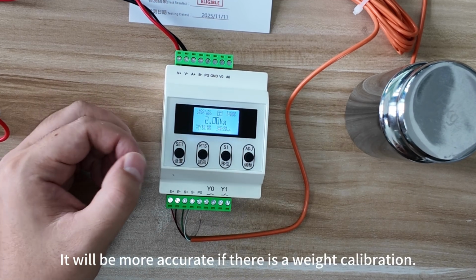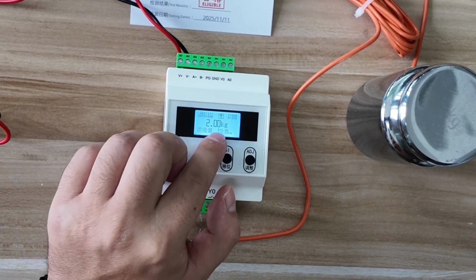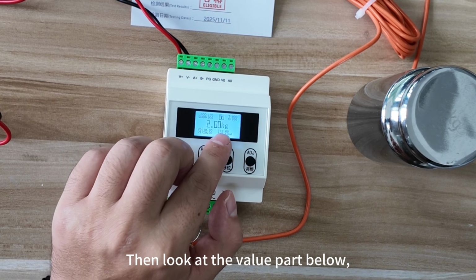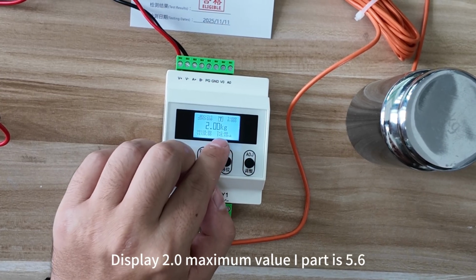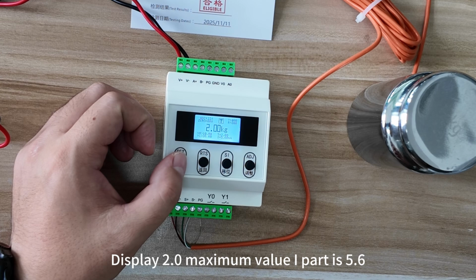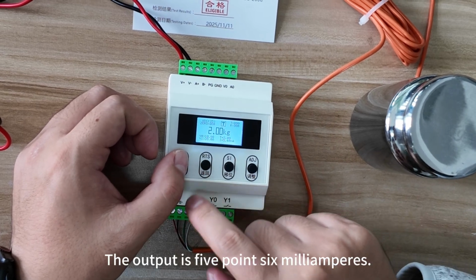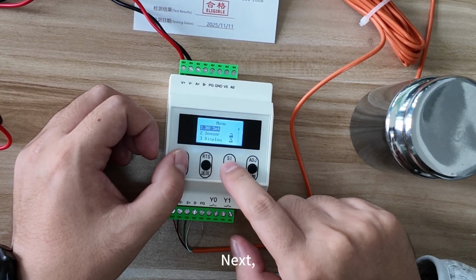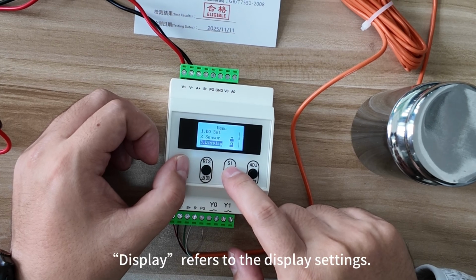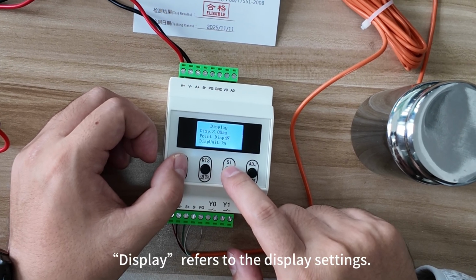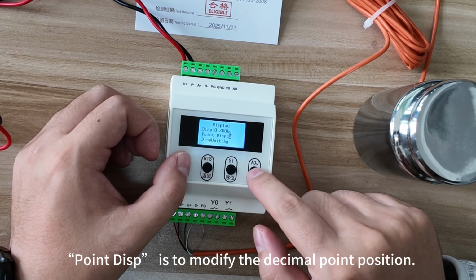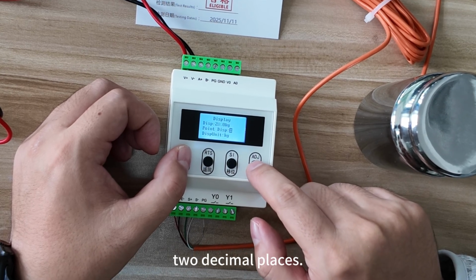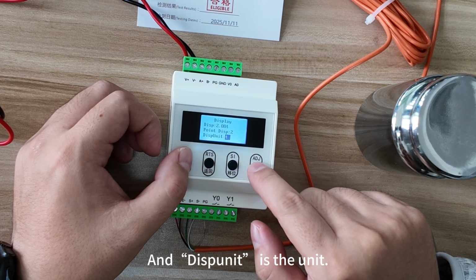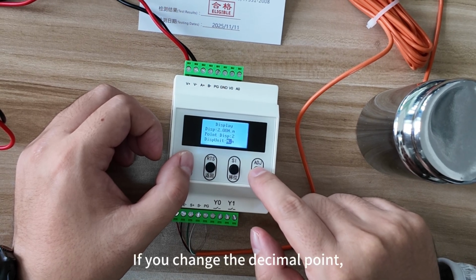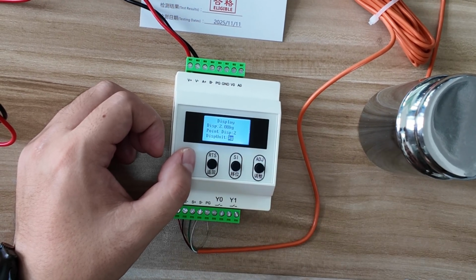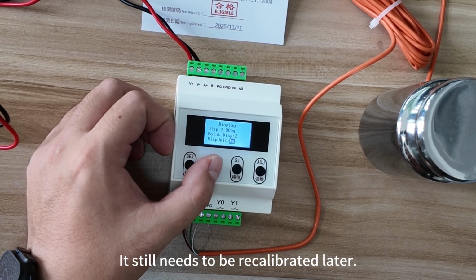It will be more accurate if there is a weight calibration. Then look at the value part below. Display 2.0, maximum value, I part is 5.6. The output is 5.6 milliamperes. Next, display refers to the display settings. Point disp is to modify the decimal point position, 2 decimal places, and DispUnit is the unit. If you change the decimal point, it still needs to be recalibrated later.